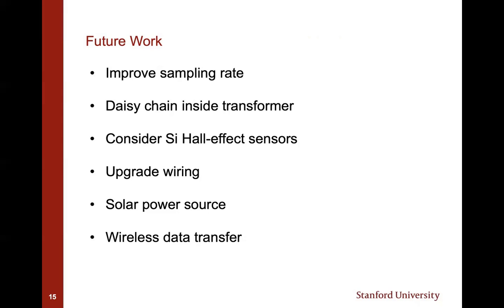So I mentioned earlier, the wiring would have to be upgraded to survive within the oil of a transformer, but of course that's a step we did not take since we only conducted tests on dry transformers. Now, while this proof of concept ran on a 3.7 volt LiPo, I would suggest that its extremely low power usage could probably be kept up by a small solar panel mounted on the outside of the transformer.